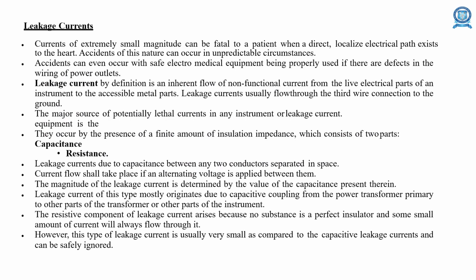Leakage currents. Currents of extremely small magnitude can be fatal to a patient when a direct, localized electric path exists to the heart. Leakage current is the inherent flow of non-functional current from the live electrical parts of an instrument to the accessible metal parts. The major source of potentially lethal currents in any instrument is leakage current. Leakage currents are due to capacitance between any two conductors separated in space. The resistive component of the leakage current arises because no substance is a perfect insulator and some small amount of current will always flow through it.